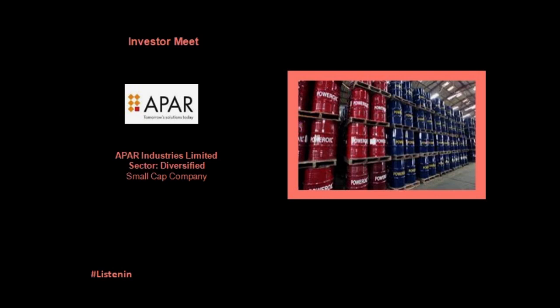Because this is becoming such an acute, difficult problem, utilities worldwide have been forced to reconductor - that means replacing the old conductor with one that can transmit double the amount of power, while the entire tower infrastructure remains the same. There is already a certain ground clearance, the distance from the ground to the transmission line conductor, that cannot be violated, because we don't want anybody coming into contact with a live line and creating a safety issue. So to maintain that ground clearance, the product used is called a low sag conductor.